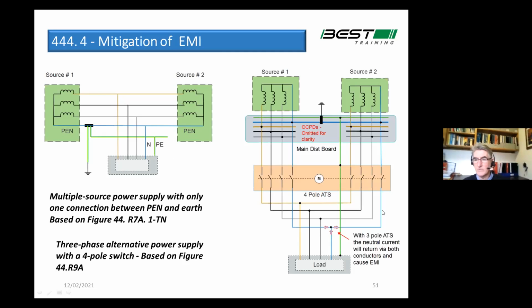The one on the right is one that was kind of new to me. I never really thought about it, to be honest with you, even though I've been specifying automatic transfer switches for years. It shows a main board fed with 2 transformers, an open coupling arrangement, but with a common neutral. And it shows you coming down to a critical load down here, fed through an ATS. Anyone who's not familiar with an ATS, it's an automatic transfer switch, which just automatically transfers from the A supply to the B supply. And what they're telling us is you should only be using 4-pole. In the industry, it's quite common to specify 3-pole. And if you use 3-pole, here's the problem.